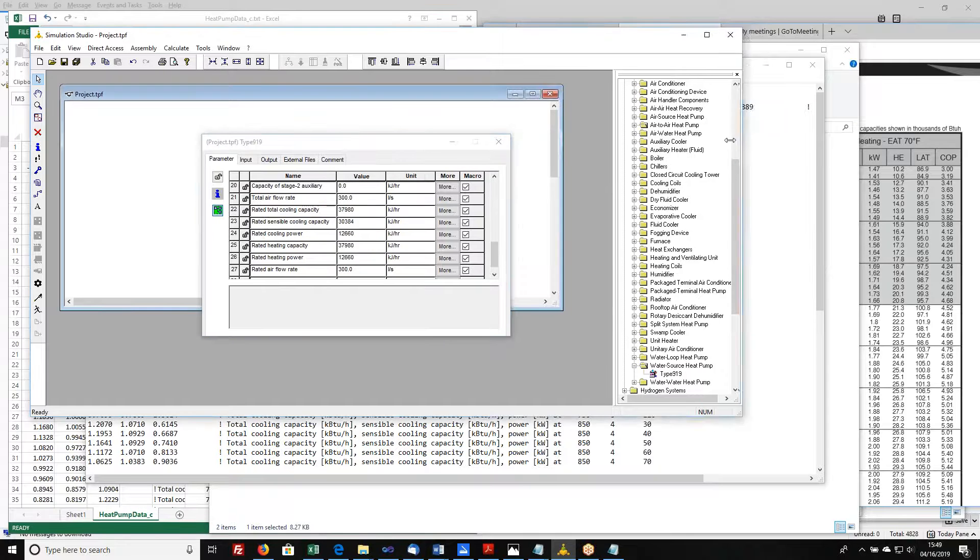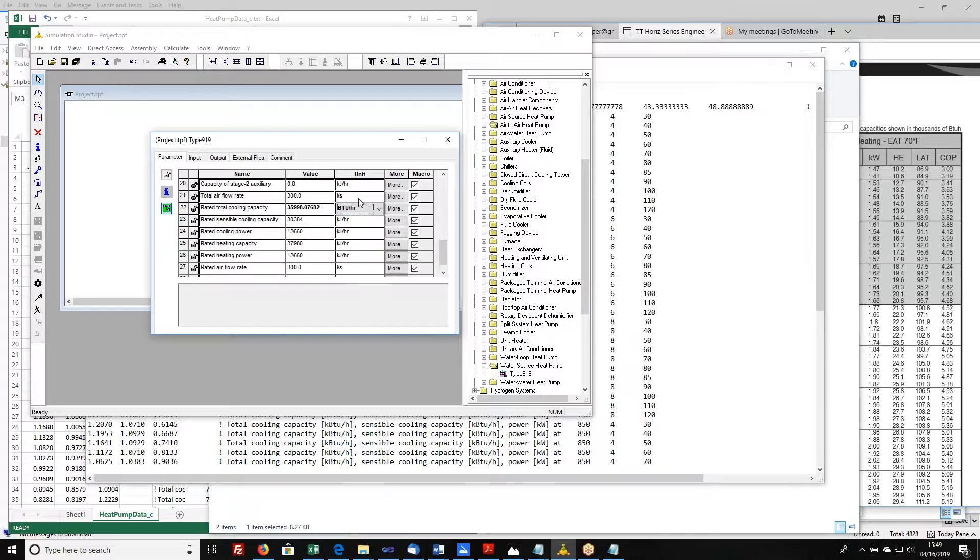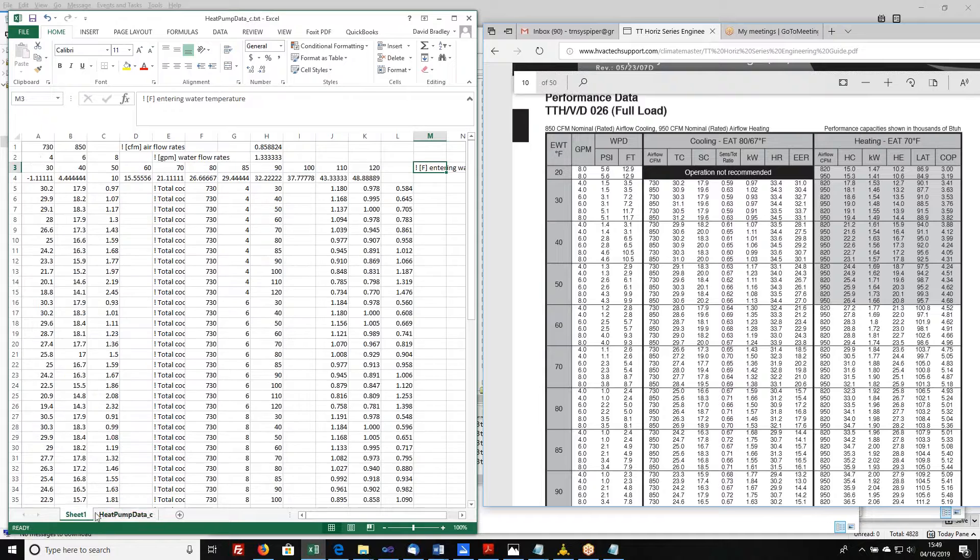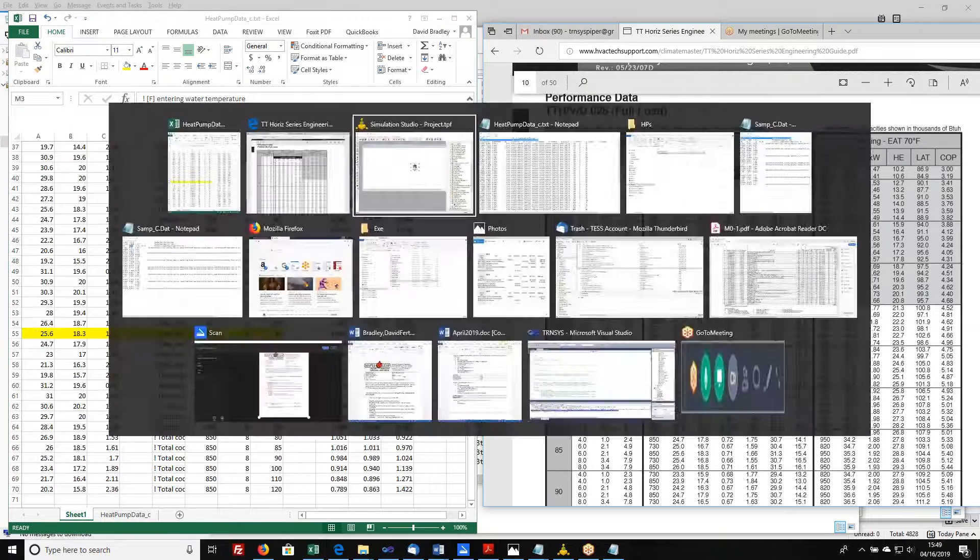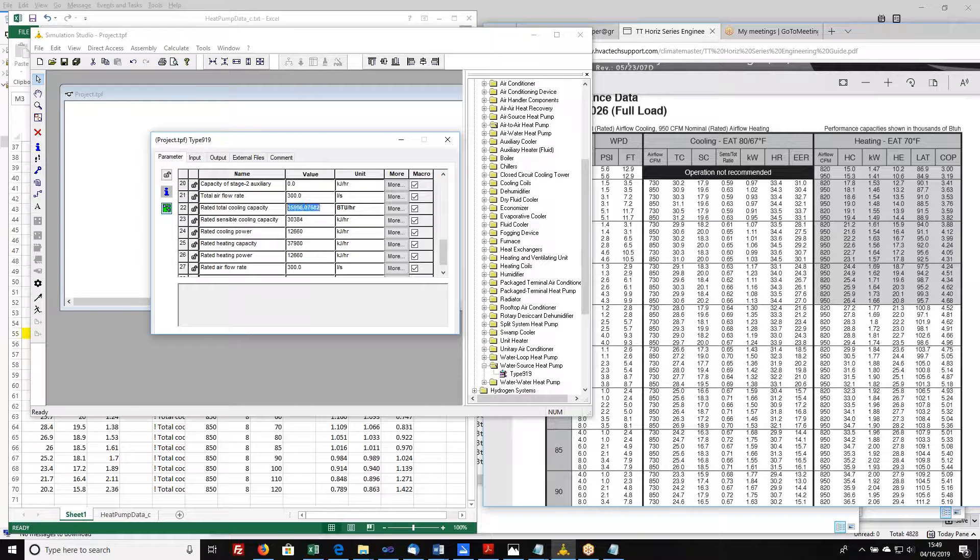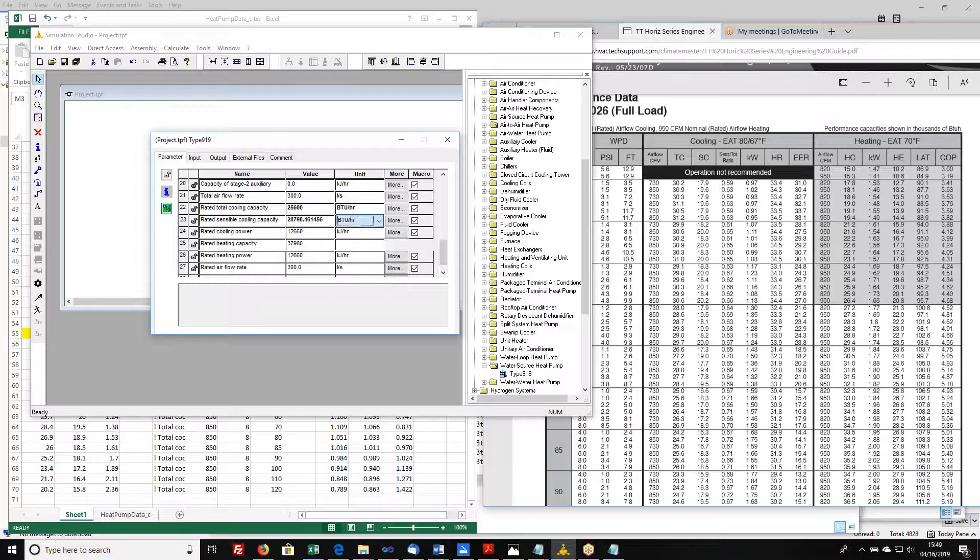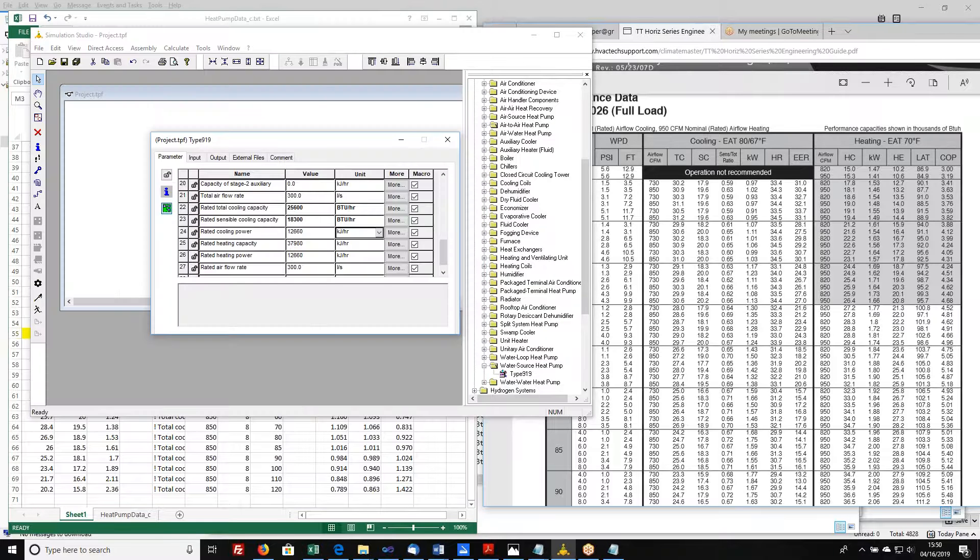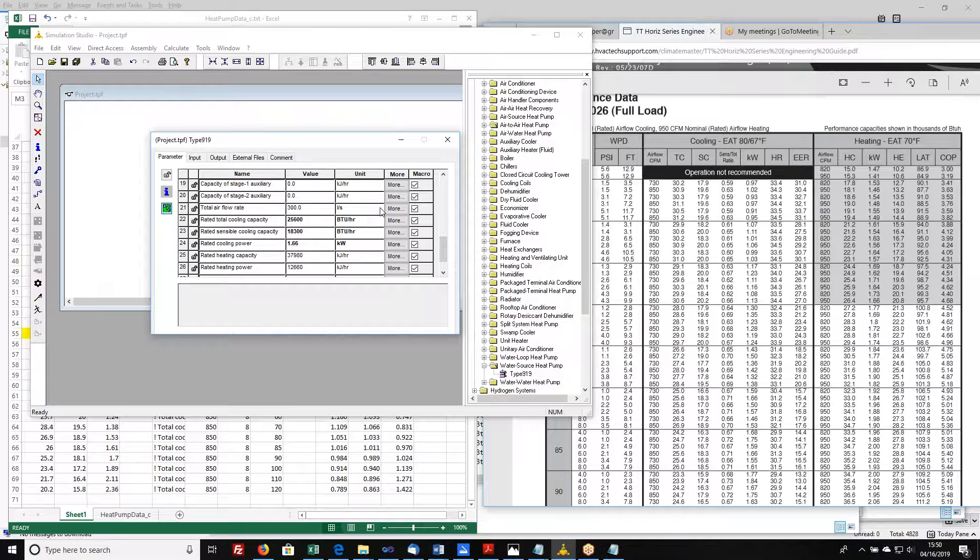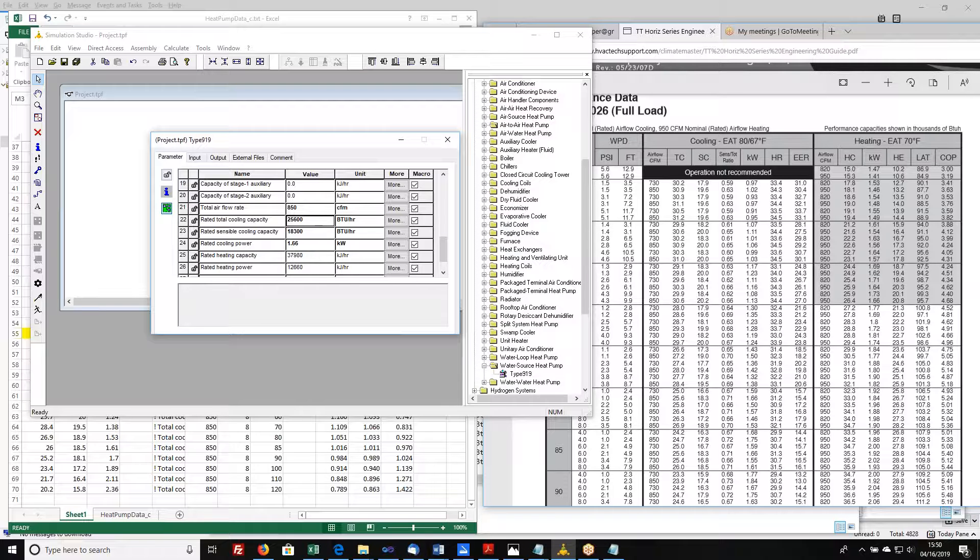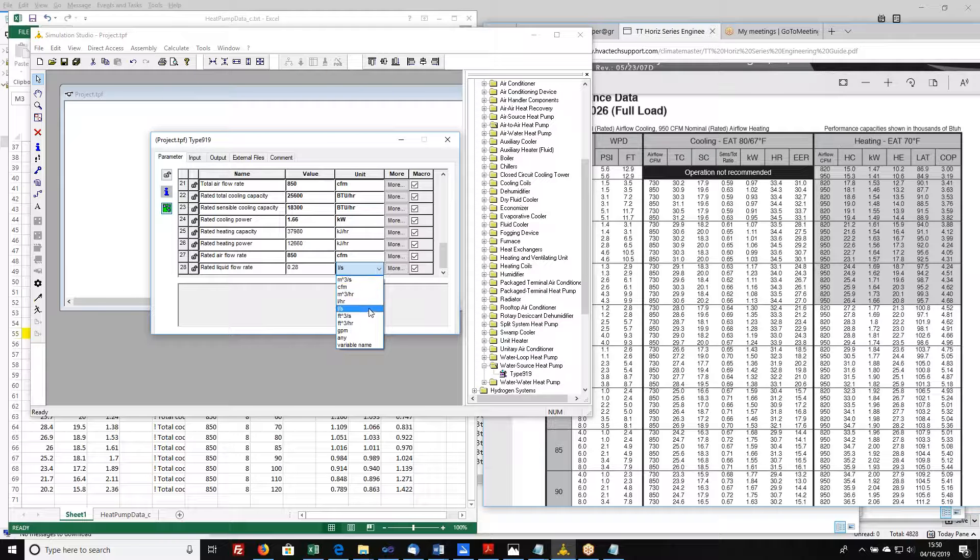So I'll show you how that works. So we've just done cooling and our device here, you'll remember, so we can go back to our Excel and the unnormalized one, was 25.6. So I need to set this. I'm setting it to BTU per hour, 25,600 BTUs per hour. The rated sensible capacity, 18.3. And the rated power, that was in kilowatts. There we go. Now, again, I'll have to repeat this for the heating side of the heat pump. Should make sure to set this correctly. CFM, and instead of 635, we said this was 850. And set that here as well. And we've got to set the rated liquid flow rate as well. GPM was 6. Okay.